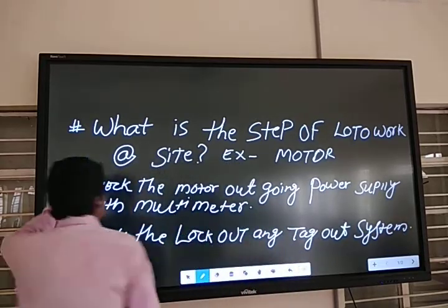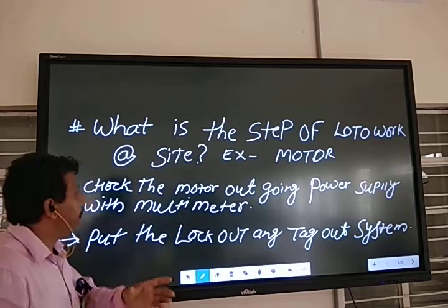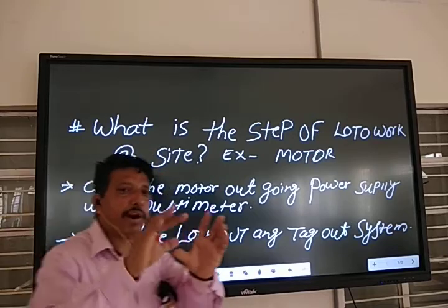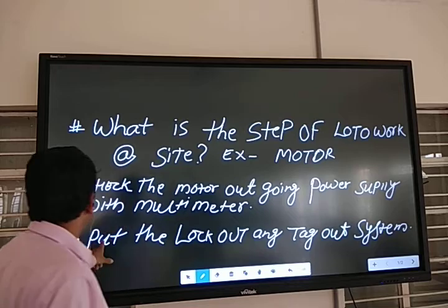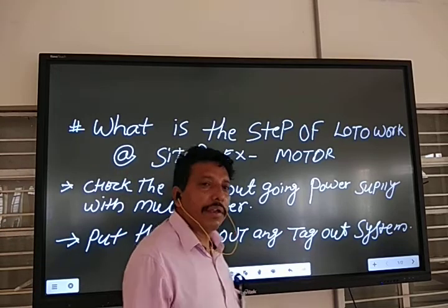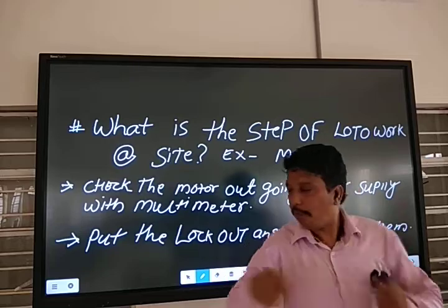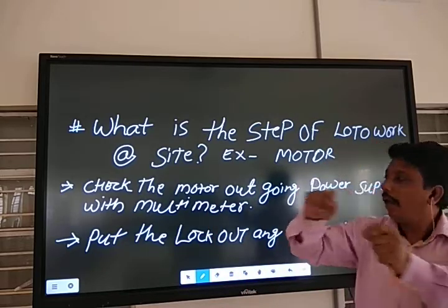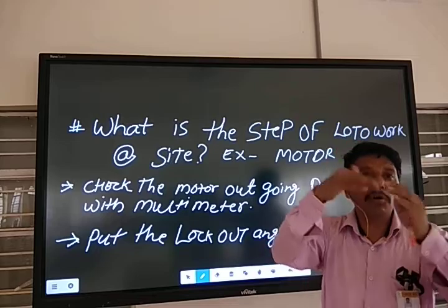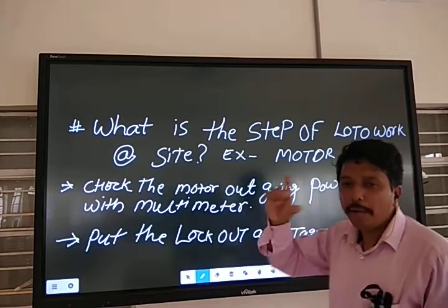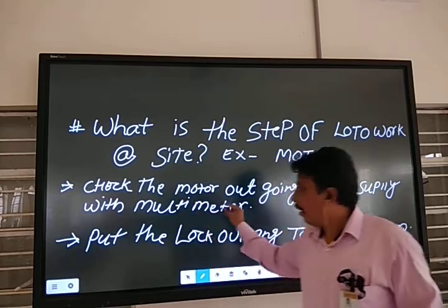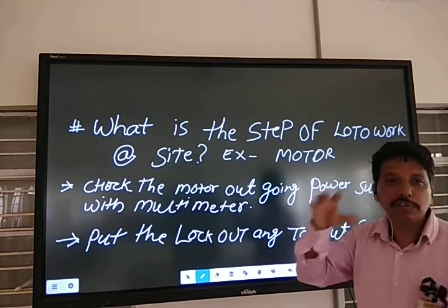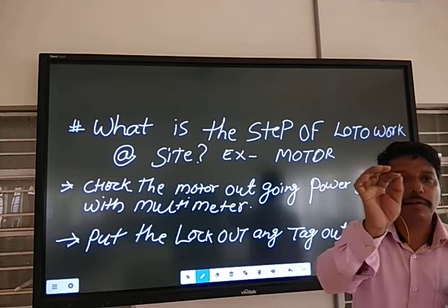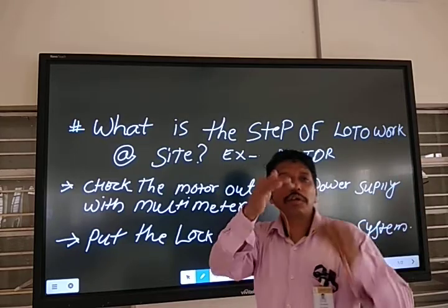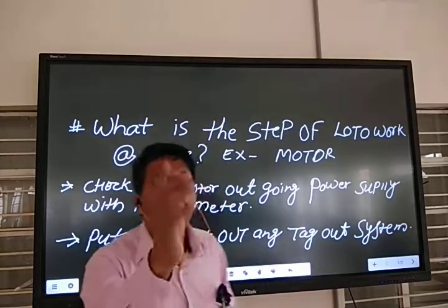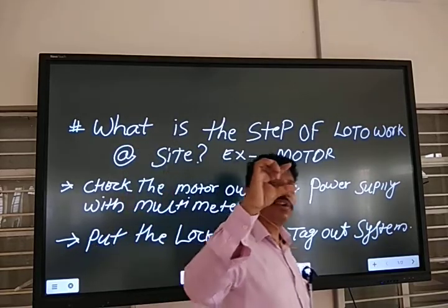If everything is okay and power is not coming, you check with the multimeter to confirm. This means you put the lockout and tag out on this panel: stop the main switch, close the window door of the panel, and put the padlock, then put the tag symbol also. The symbol reads that maintenance work is in progress, so don't touch here. This type of sticker is placed for safety.